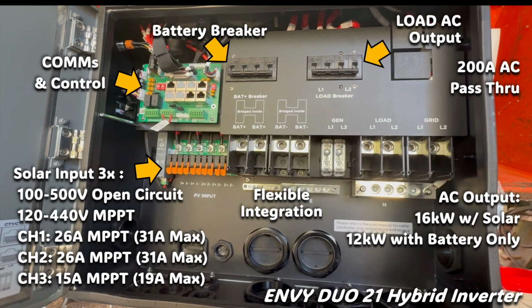Next up, load AC output breaker. This system has that built in as well. And then the AC pass-through is 200 amps, so you can use 2/0 aluminum cable here, 2/0 copper or aluminum, I should say, to fit in there for handling the load. The continuous AC output in off-grid mode is 16 kilowatts with the sun shining and 12 kilowatts with only batteries. And that's nice. That's equivalent to a 50 amp breaker. So plan accordingly if you're trying to design a system for off-grid use.